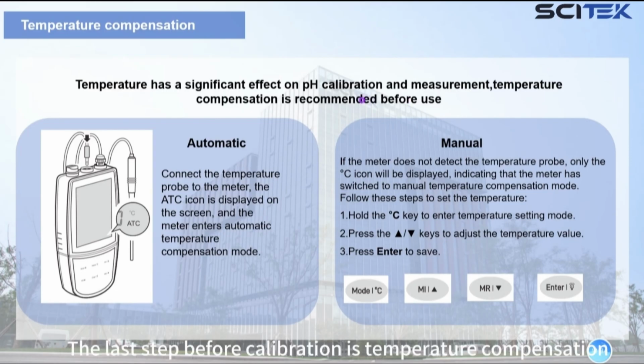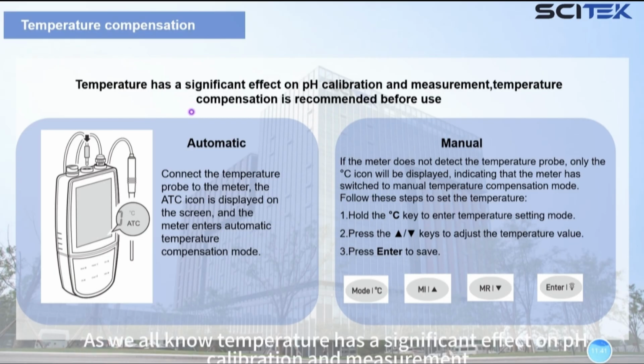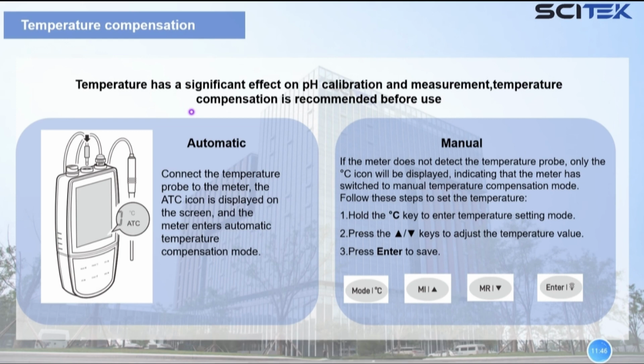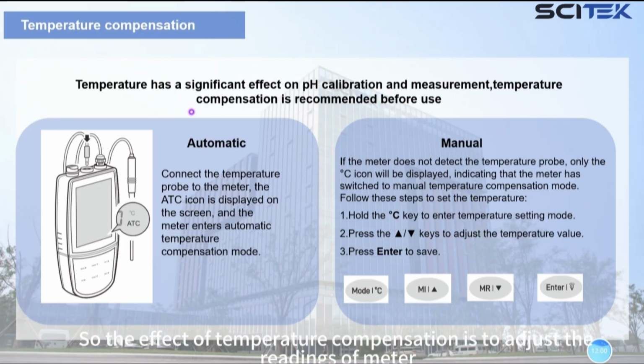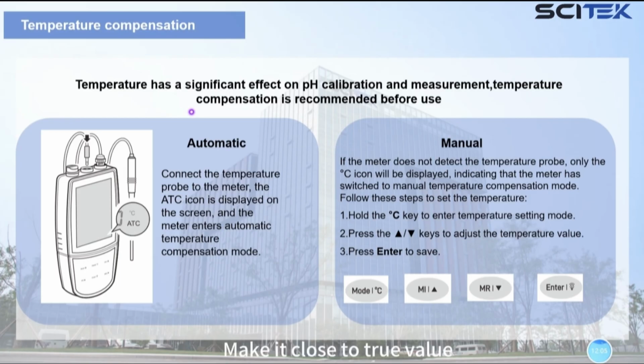The last step before calibration is temperature compensation. As we all know, temperature has a significant effect on pH calibration and measurement. When the temperature changes, the pH and the pH electrode sensitivity will change. In this condition, the meter may measure a wrong result. So the effect of temperature compensation is to adjust the readings of the meter, to make it close to the true value.